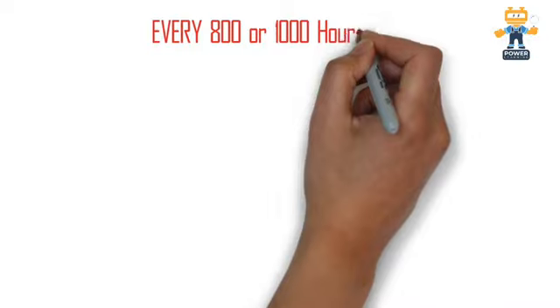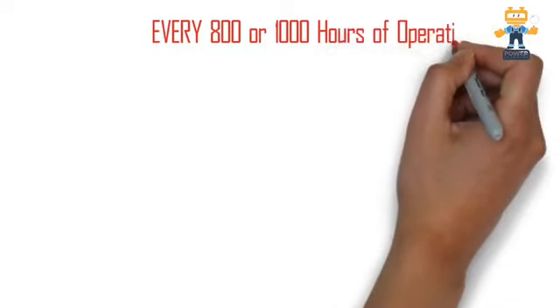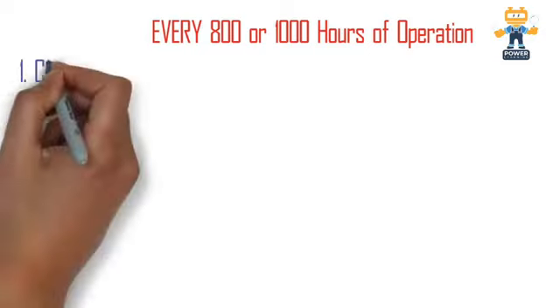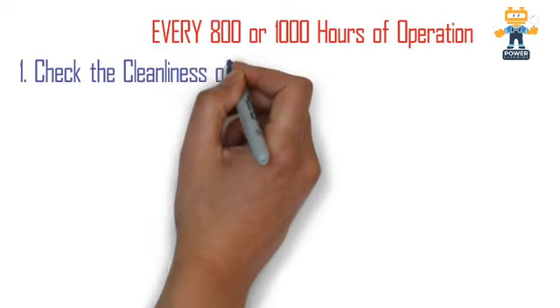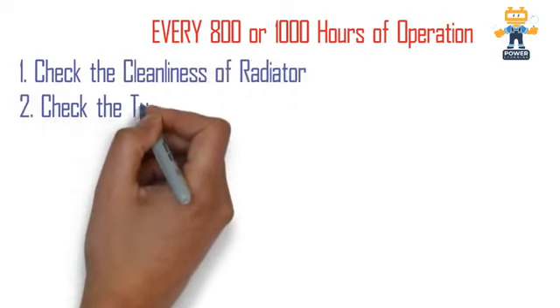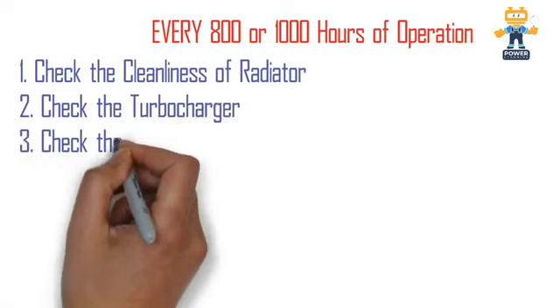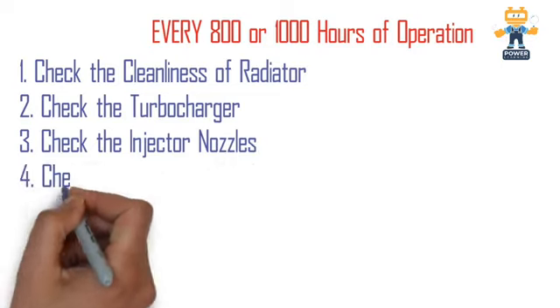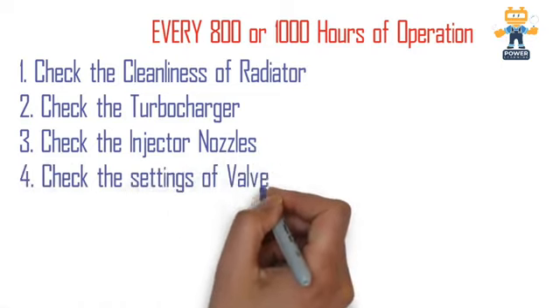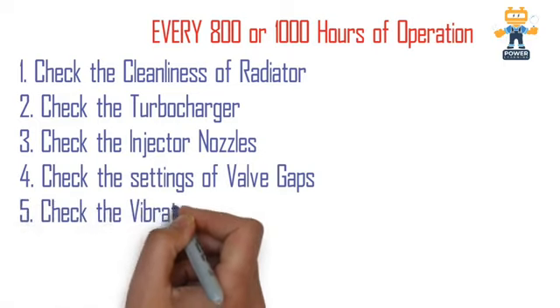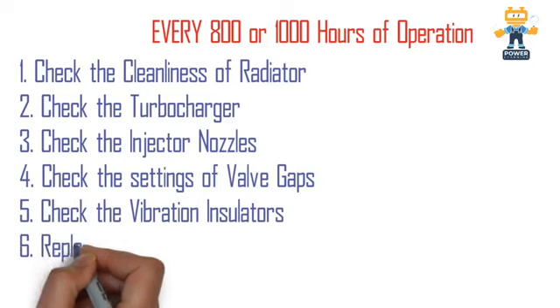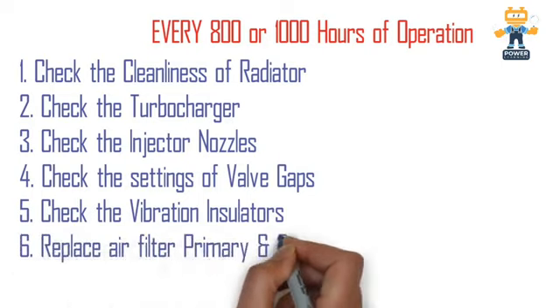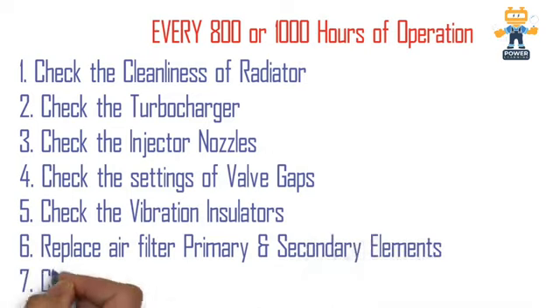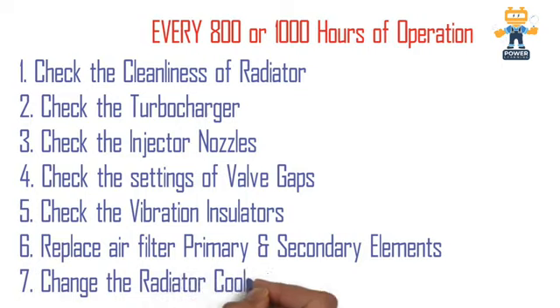Now we will discuss every 800 or 1000 hours of operation. You have to follow these steps after every 800 or 1000 hours of operation as per your site condition. Some sites are very clean and some sites are very dirty, depending on their environmental conditions. So we have to follow these points every 1000 hours of operation. Check the cleanliness of the radiator, check the turbocharger physically, check the injector nozzle by inspection, and check the settings of the valve gaps. These are very important points. Check the condition of the vibration isolators, whether they are okay or not. Replace the air filter primary and secondary elements every 800 or 1000 hours as per your site, and check the radiator coolant level also.